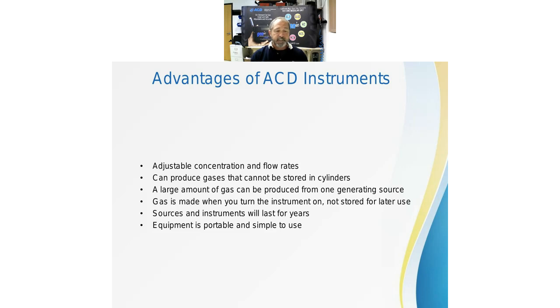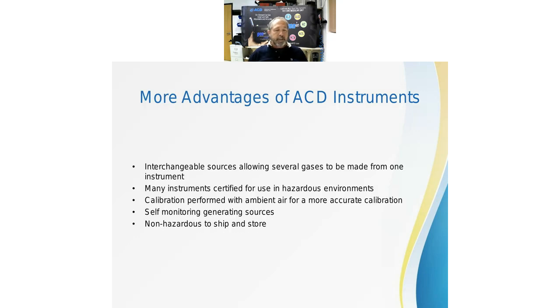The sources last for years, and the instruments are portable and easy to use. There are user interfaces and displays in the instrumentation that walk you through how to set them where you want them, to calibrate the equipment that you're using. Some other things about these calibrators: you can pop different sources in and out. So you can insert a chlorine dioxide source into one unit. You can take it out, sort of like an inkjet cartridge in a laser printer. You take one out, put another in, so you have one instrument and you can generate several different gases.